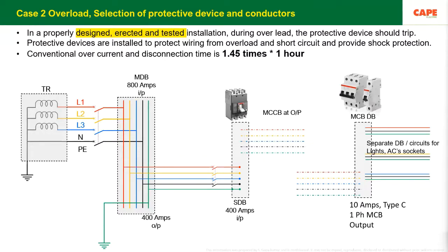Actually, electrical engineers shall not make this claim, because an electrical engineer knows that there are protective measures implemented in a certain installation, and the protective devices are supposed to operate before the electrical installation causes a serious accident. So we have a lot of protective devices in our network. Nowadays we have MCCB, MCBs and all, but in olden days we had fuses. Of course, fuses are also equally effective if they are appropriately selected and installed. Very important. If we put an overrated device, of course, it may not work. If we put an underrated device, then it may trip unnecessarily.